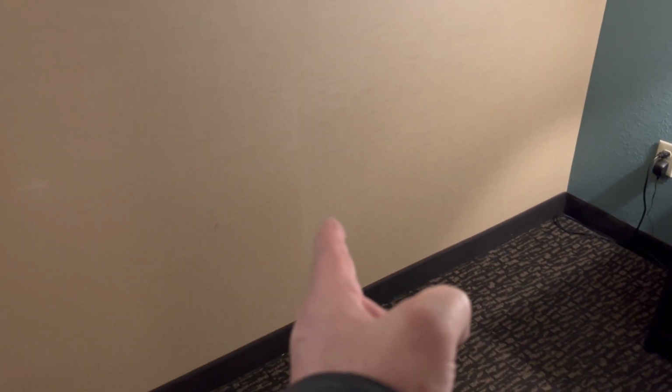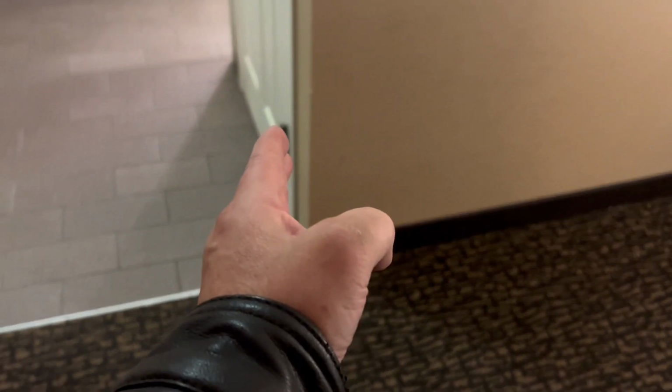But let's start over here now. And now let's measure 6 feet. And I'm going to come out to about here. So I'm going to need another receptacle outlet over here so that I'm within 6 feet of where that wall is starting, where that door is.